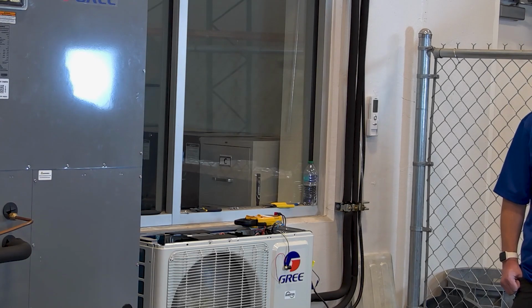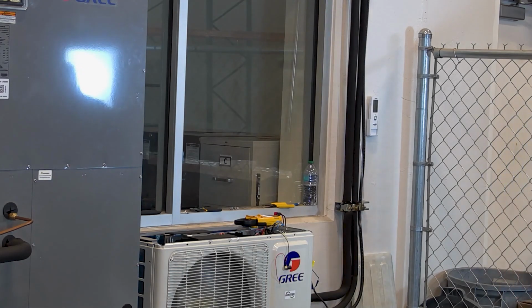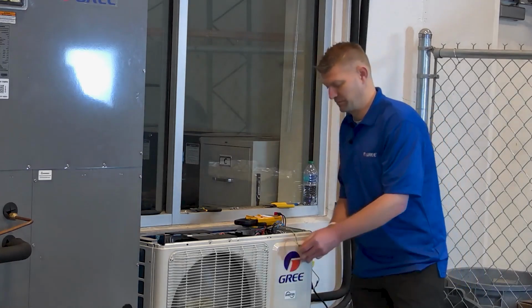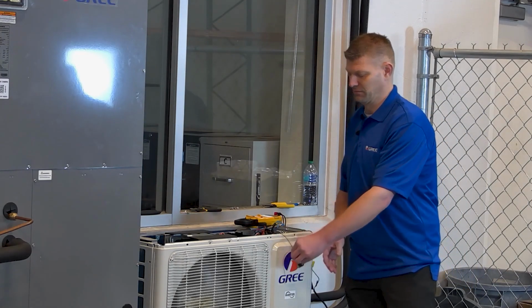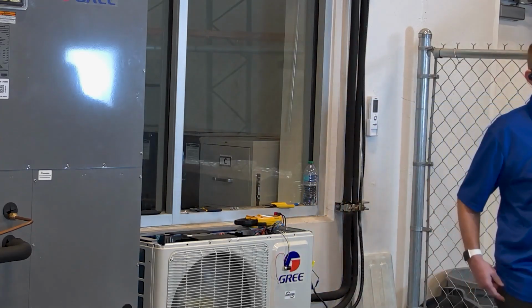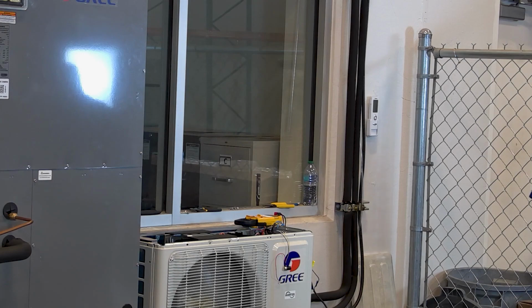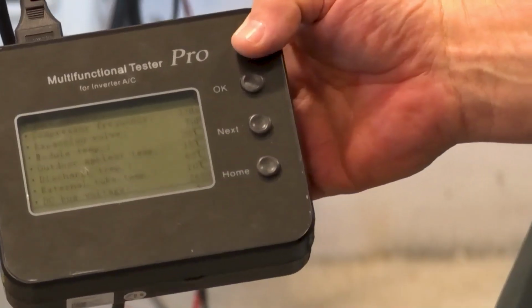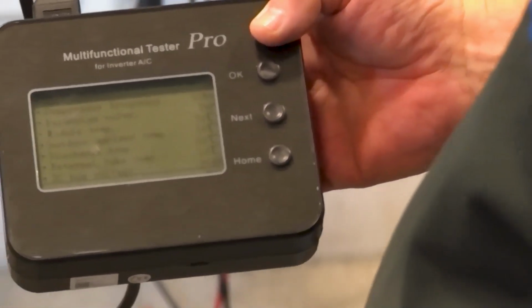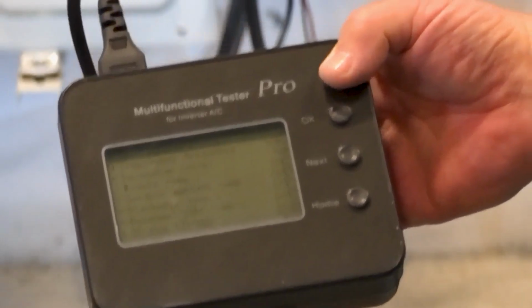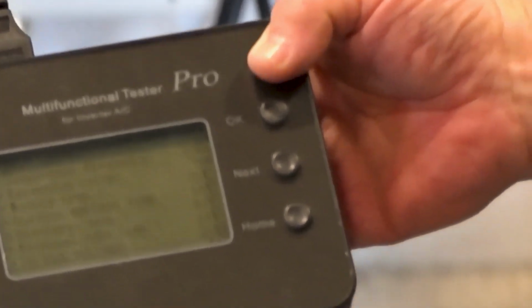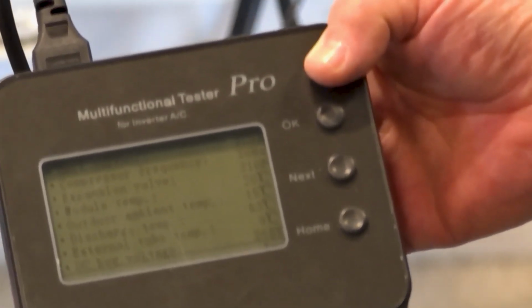Discharge temperature now is at 43 degrees Celsius. All right, so let's take that up a little bit more. 63 degrees Celsius. 148. So we're getting pretty hot. I think the 148 discharge temperature, in my experience, guys, because I've dealt with this a lot, that's not an ungodly discharge temperature, okay? I don't know if the machine would fault out on that or not. But when you start getting at like 175 plus, that's an awful hot discharge.